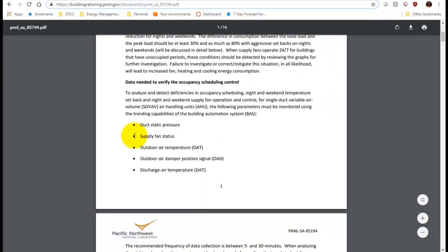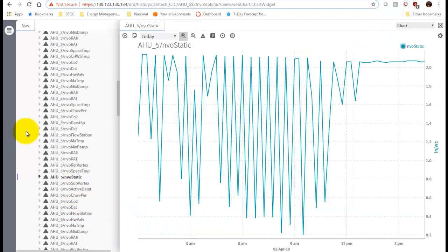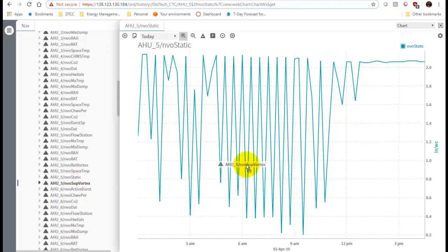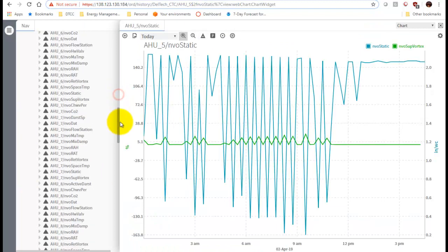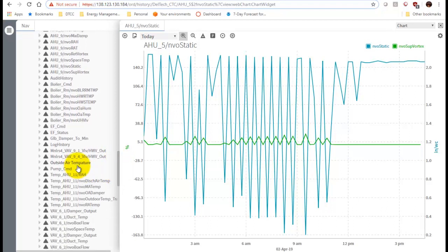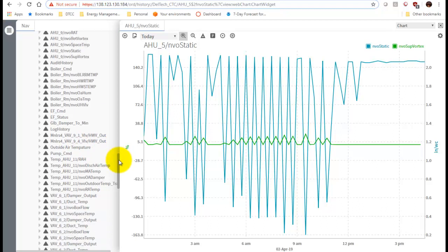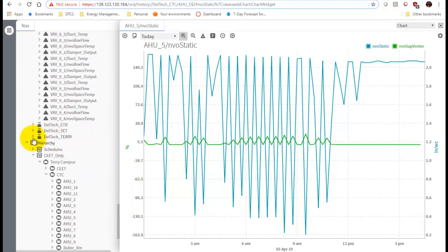Next we're going to do supply fan status, but I don't think we have one here. We can double check - we have CO2, chilled water valve percentage, discharge air static setpoint, discharge air temperature, a flow station, mixed air temperature, mixed air damper, return air humidity, return air temperature, return fan vortex, space temperature, and supply vortex. The closest thing we have is the supply vortex, so we'll put that in. For outdoor air temperature, it turns out the outdoor air temperature in the CTC building is not good - it actually gives you relative humidity for some reason.